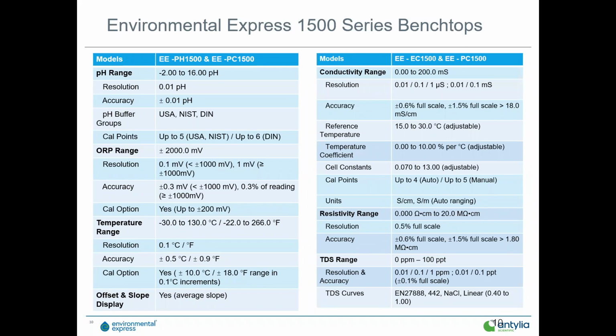So for conductivity, a 0 to 200 millisiemens, so it's a full range. It's got 5 different resolutions. It's got 5 different ranges. It's a technique that manufacturers use to really improve the overall accuracy. In this case, 0.6% full scale. Used to be, years ago, 2 and 3% full scale was a decent meter. Now it's got to be 1% or below.